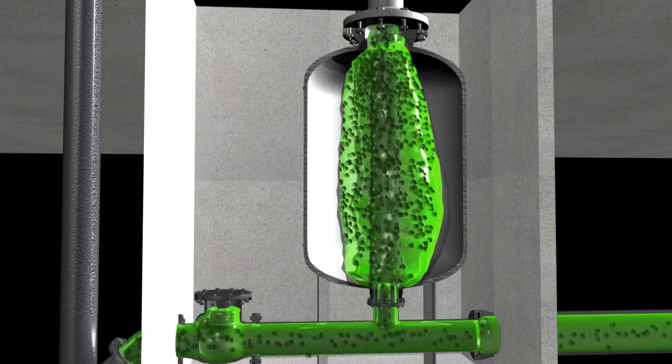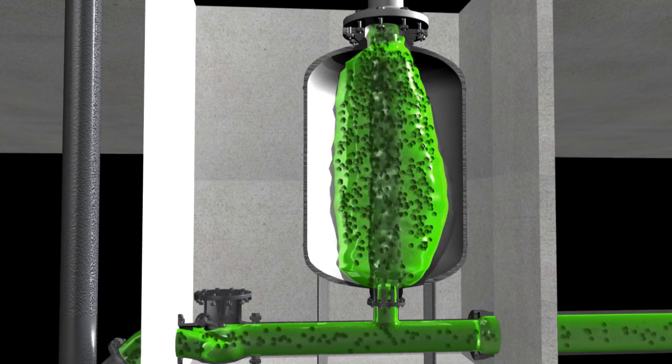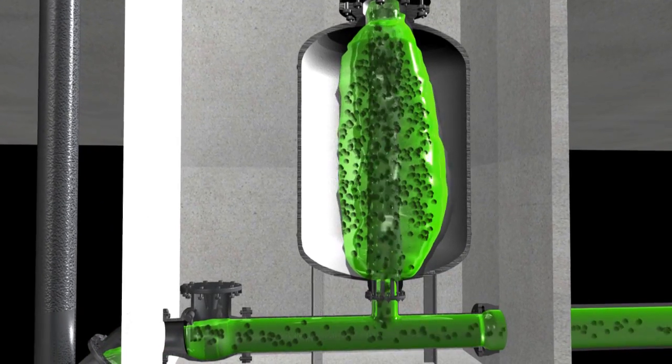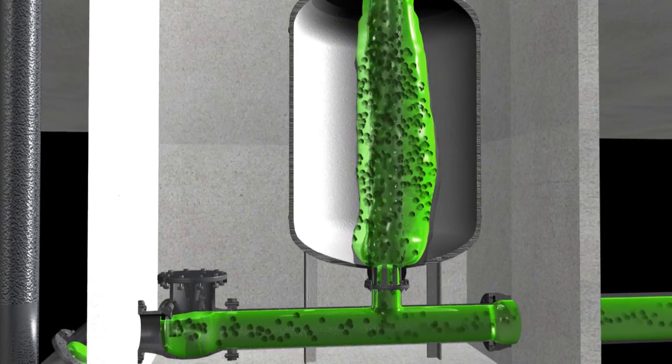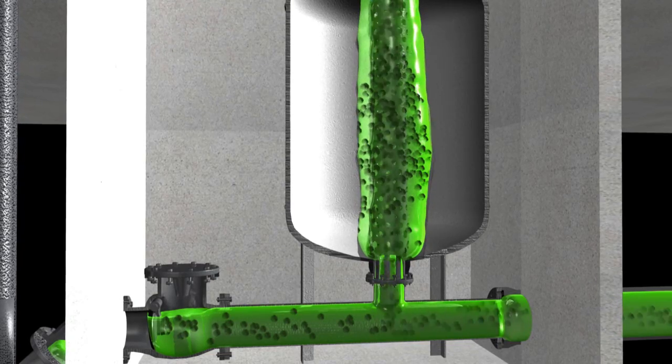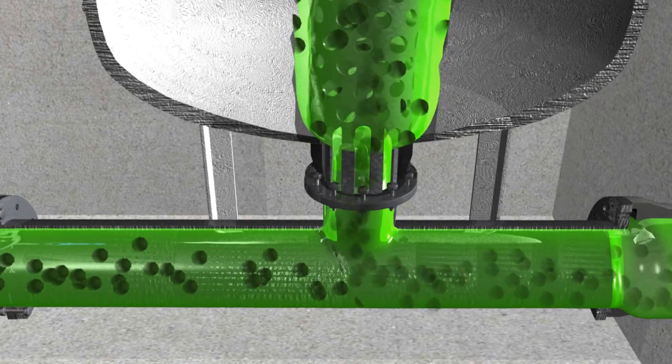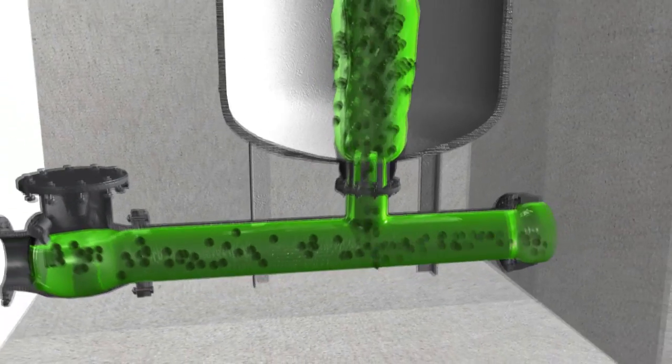When the pump shuts down, the tank's gas pressure acts on the bladder to provide uninterrupted flow in the piping from sewage in the bladder, simultaneously closing the check valve to prevent column separation. The solids discharging from the tank are channeled through the slots in the perforated column.